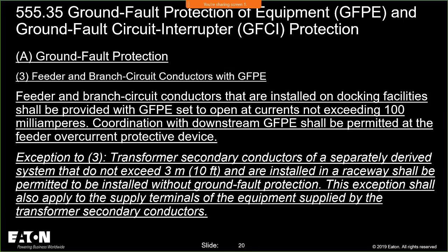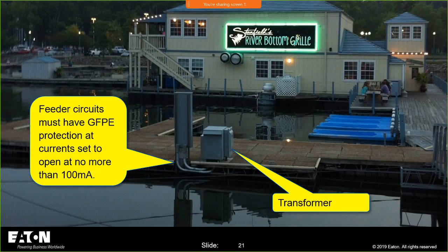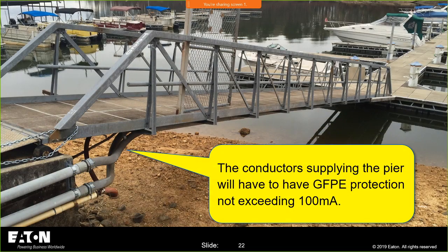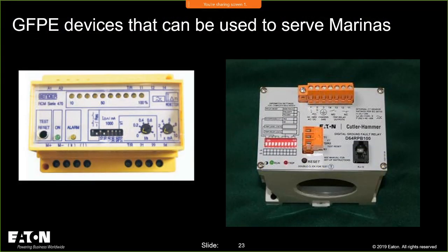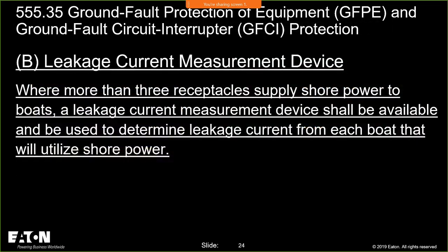But that 100 milliamps is probably going to detect leakage current well before they come in contact with anything. Those are just pictures of all the feeders that go out, and there are solutions—Bender has a relay, we have relays, Eaton has relays. I know we use a lot of the Bender products as well. Those are solutions on the market to serve that need.